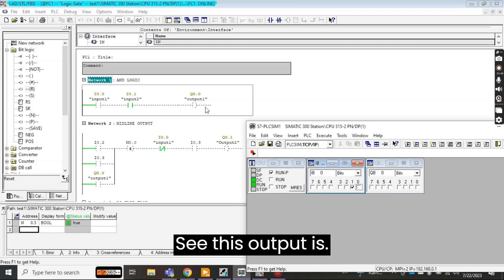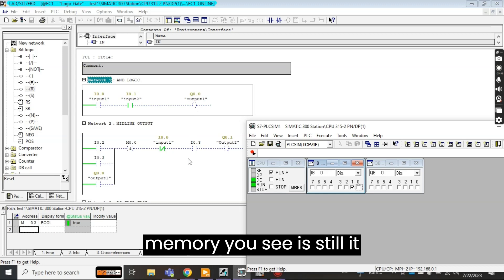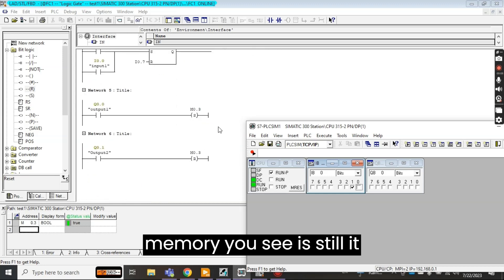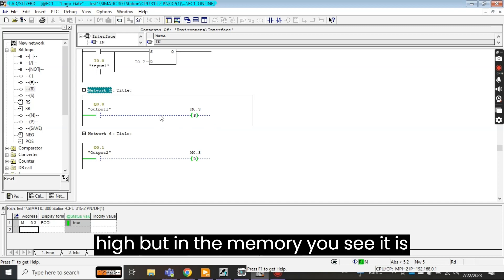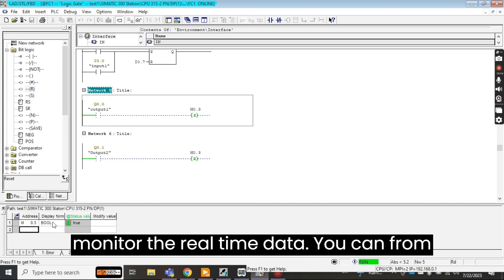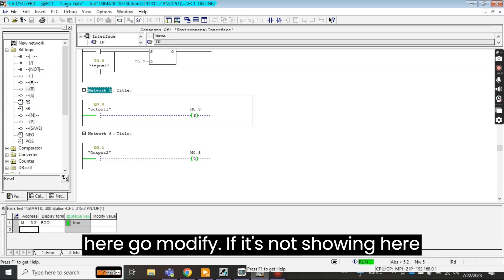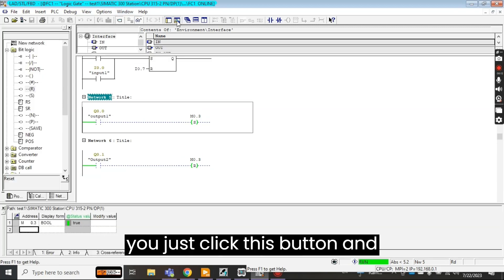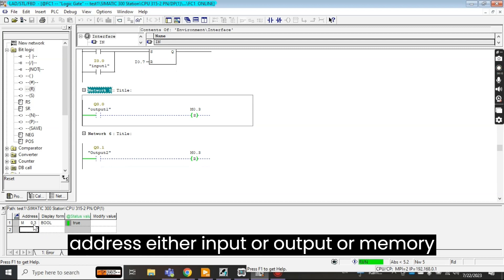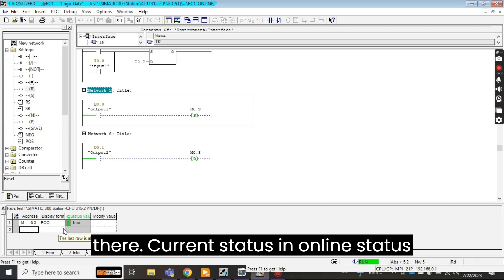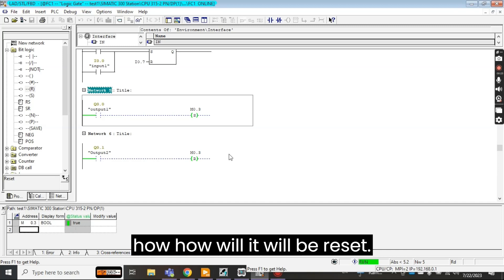See this output is now low, Q 0.0, but the memory you see still it is here. Here you can see it is not high, but in the memory you see it is still true. M 0.3, this is actually to monitor the real time data. You can from here go to modify. If it's not showing here you just click this button and from here go to modify and write any address, either input, output, or memory bit or byte whatsoever, and you will see their current status in online status. This is still true.